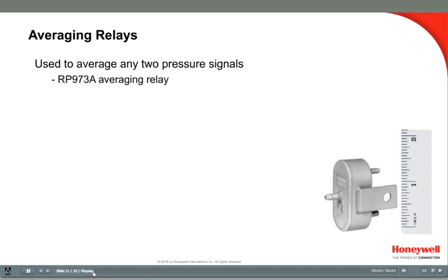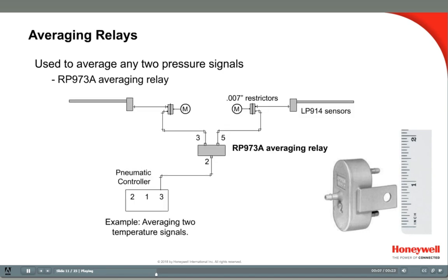Averaging relays are used to average two pneumatic pressure signals. There are three ports on the RP-973. The two inputs are 3 and 5, and the averaged output is port 2. The RP-973A can be used to average two LP-914 sensor signals to obtain an average temperature.